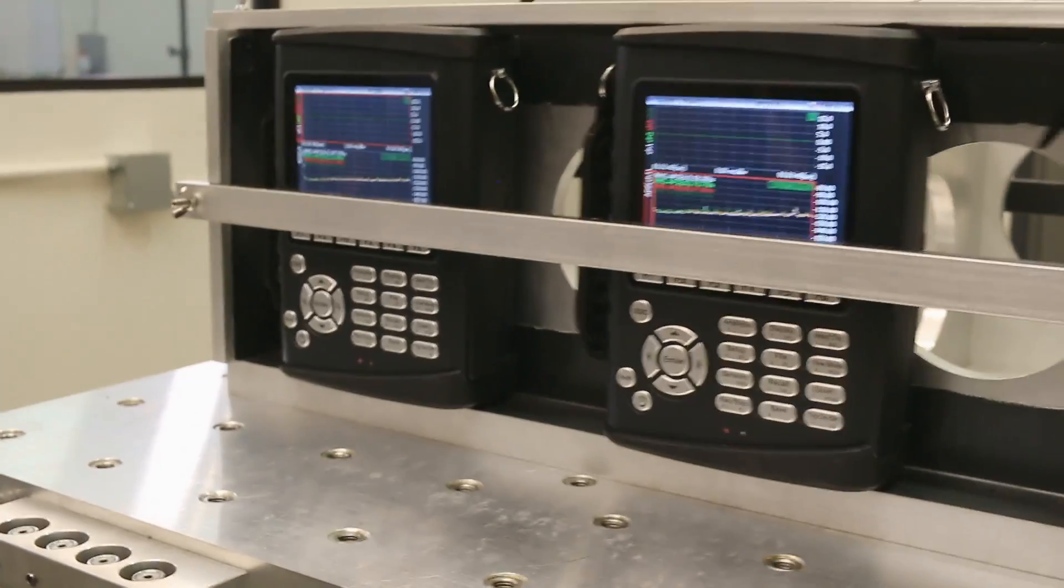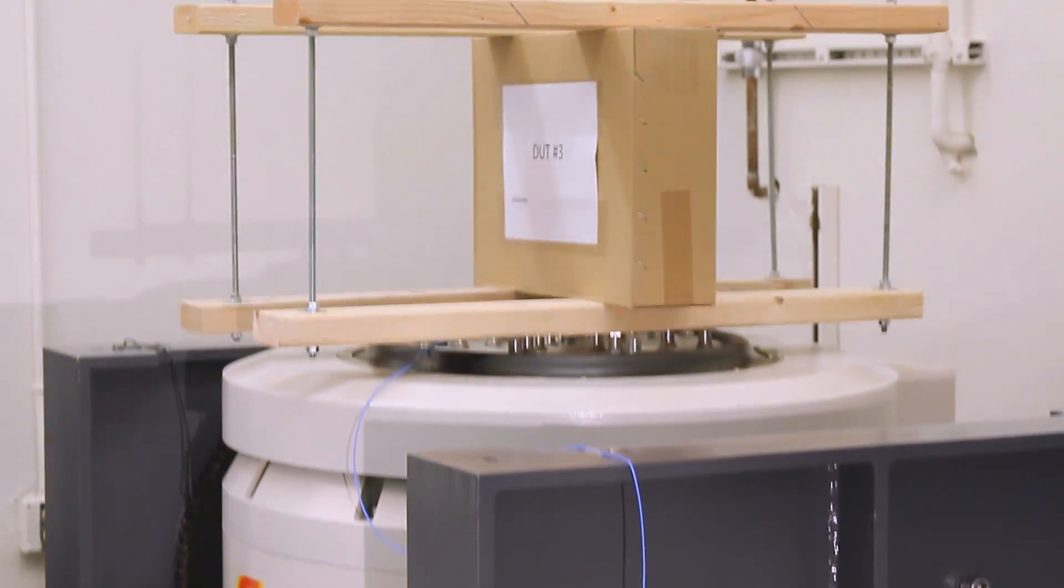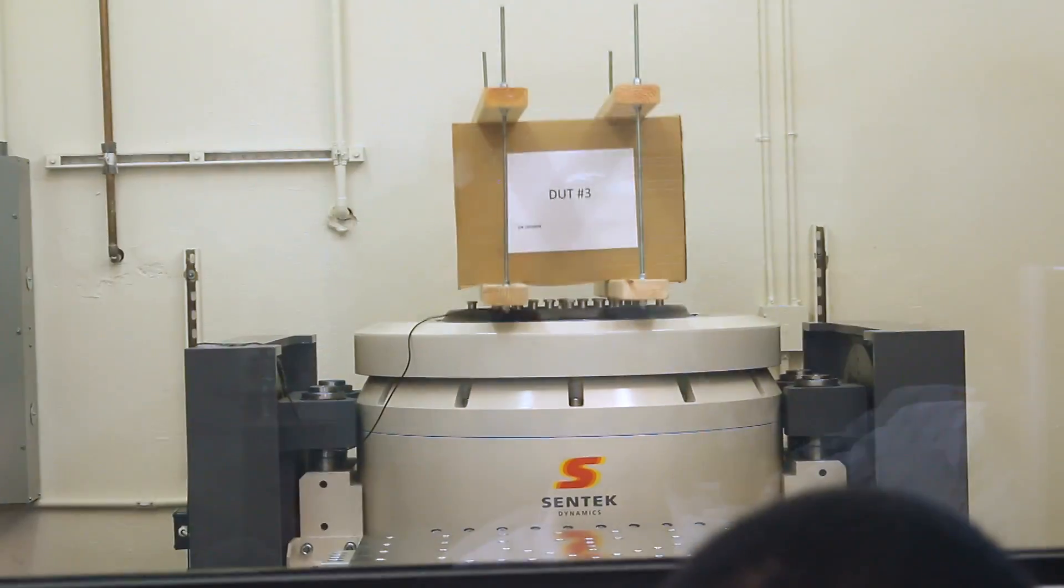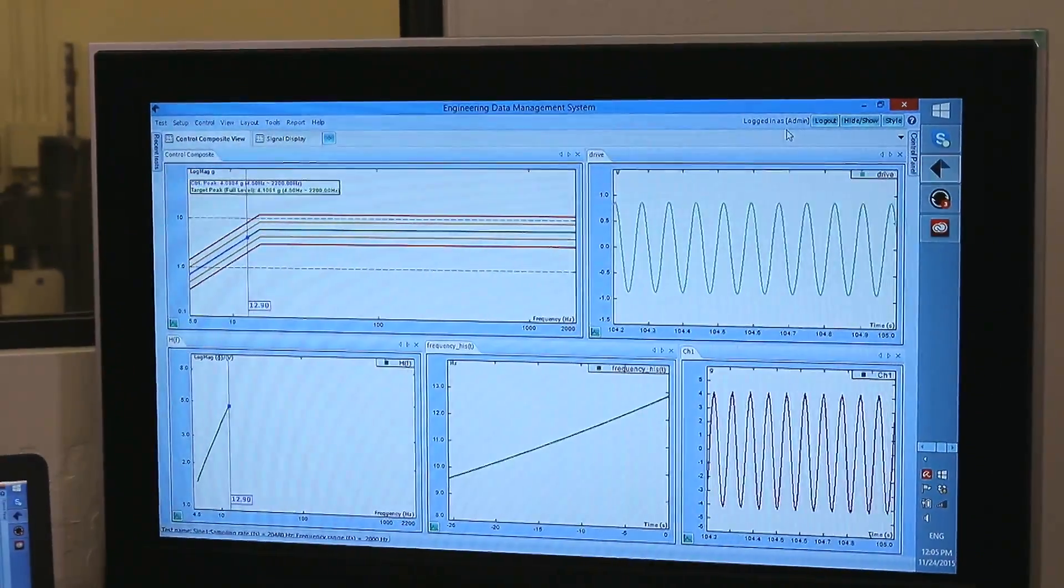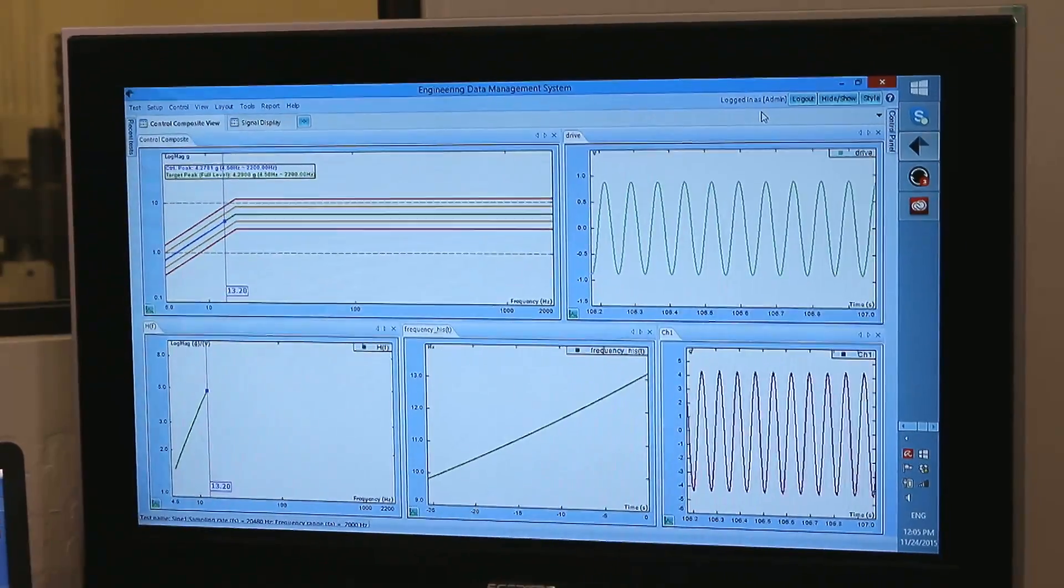The swept sine control process consists of generating a sine wave output to excite the device under test. When the control signal input amplitude is detected, the detected level and the reference amplitude are compared and the drive signal amplitude is updated appropriately.